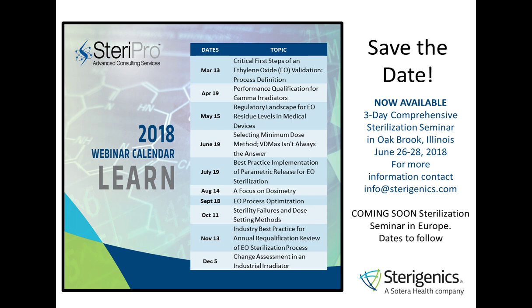So a lot of times during process definition, one of the things that you may consider performing is a simulated half cycle. Now this simulated half cycle doesn't actually go towards your validation. It can be performed in that pilot vessel, but you run it with the parameters that you're looking to run for your performance qualification half cycle. And that gives you an idea of whether you can get kill on that.